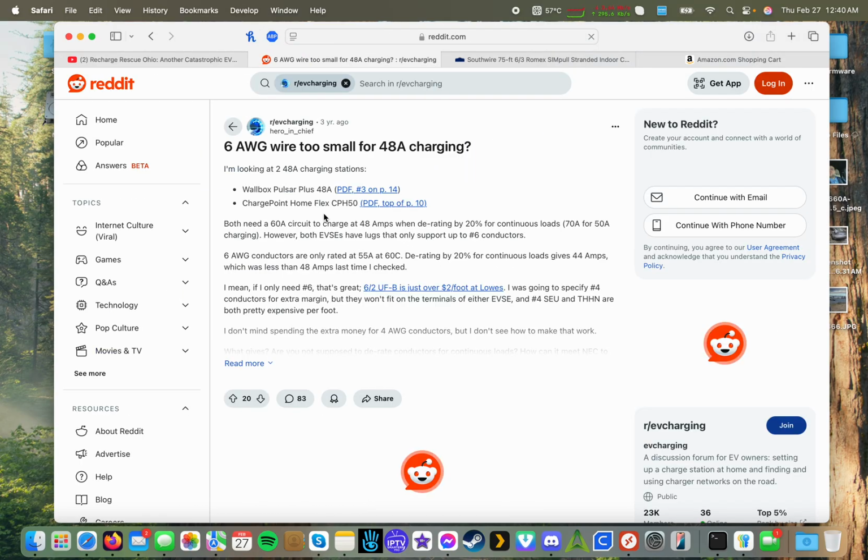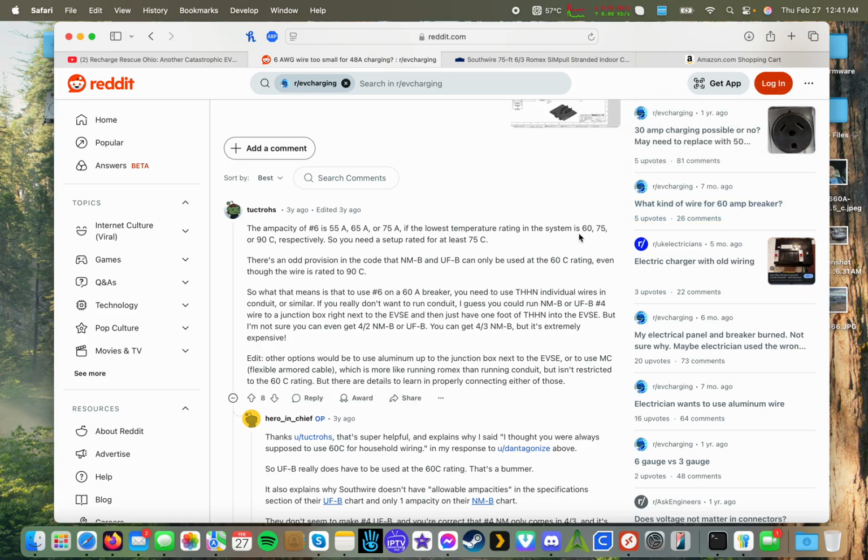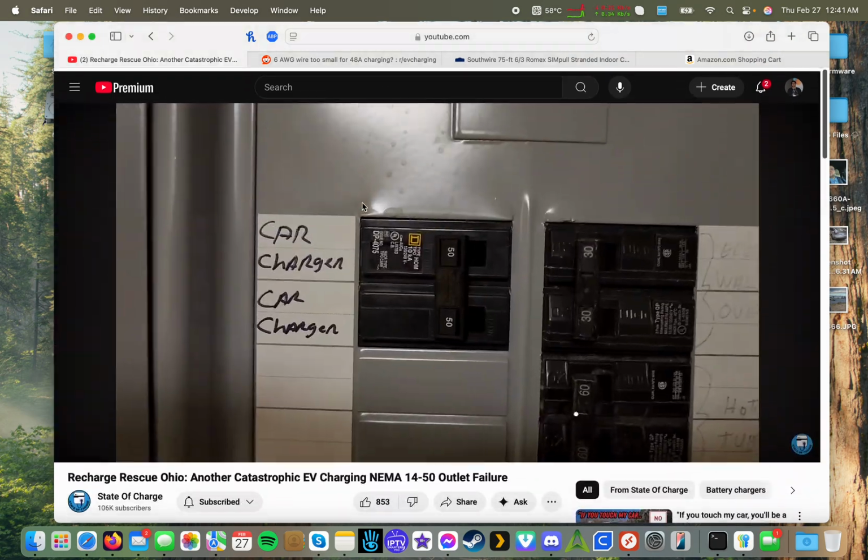Let's see, what does this one say? You sometimes will get different answers, but the general consensus is, and this guy's saying, number six is ready for 55, 65, or 75. I did see that earlier based on your temperatures. So 60, 75, and 90 C respectively. So supposedly a 90 C rated 6-gauge wire should be able to handle 75. Maybe that's why Romex is showing only 55 at 90. Maybe it is a lesser wire, but at 90 C rated copper Romex, there's no reason it shouldn't be able to handle it, unless maybe the person in this video had aluminum Romex.